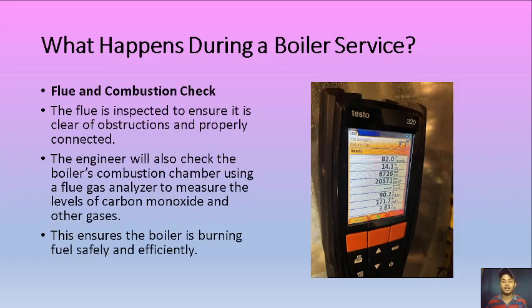Next, for flue and combustion check, the flue is inspected to ensure it is clear of obstructions and properly connected. The engineer will also check the boiler's combustion chamber using a flue gas analyzer to measure the levels of carbon monoxide and other toxic gases. So we have here a sample of a gas analyzer. In here we can see the measurements: ppm of carbon monoxide, percentage of oxygen, we have efficiency, exhaust air percentage, and CO2, carbon dioxide. So in here we can measure if the combustion is good or not. This ensures the boiler is burning fuel safely and efficiently.